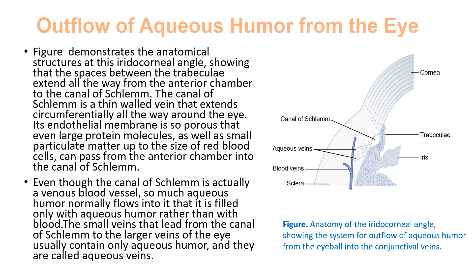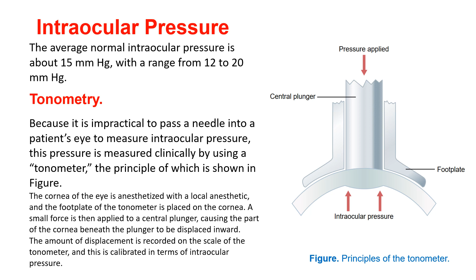Tonometry. Because it is impractical to pass a needle into a patient's eye to measure intraocular pressure, this pressure is measured clinically by using a tonometer, the principle of which is shown in the figure. The cornea of the eye is anesthetized with a local anesthetic and the footplate of the tonometer is placed on the cornea. A small force is then applied to a central plunger, causing the part of the cornea beneath the plunger to be displaced inward. The amount of displacement is recorded on the scale of the tonometer, and this is calibrated in terms of intraocular pressure.